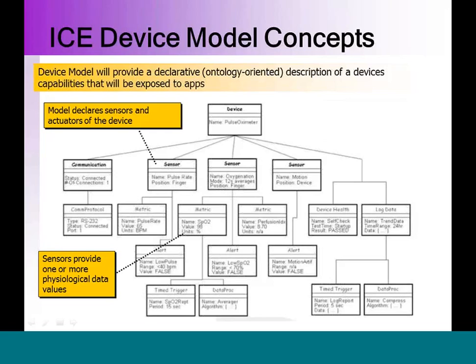And so one of the questions that's going to come up is, what sort of rich interface specification language do you use to allow an app to specify these different quality of service requirements and the capabilities needed from a particular device? That's all part of our research and is somewhat related to what the folks at NIST, including John on the line, look at. What we're trying to do is think about what it would take to extend things like 11073 interfacing technology to support the type of dynamic and secure interactions that we're talking about here.